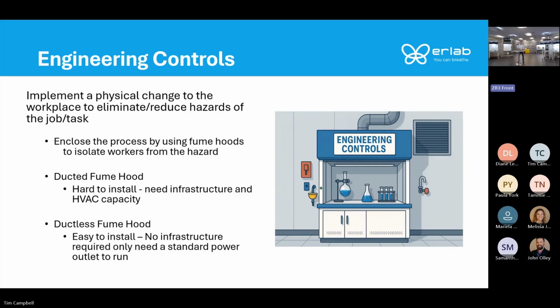The problem is if you're doing open bench chemistry, you probably don't have access to a ducted fume hood. You don't have one in your lab. Maybe it's not working. Maybe it's full of equipment. Maybe you have one down the hall that you have access to once a week. So it's just much easier to mix the chemicals or do your process on the open bench. That's where ductless fume hoods come in. They're very easy to install. You don't need any infrastructure upgrades. You just need some counter space and a plug, and you plug it in, and then you can wind up being protected by the carbon filtration on the fume hood.